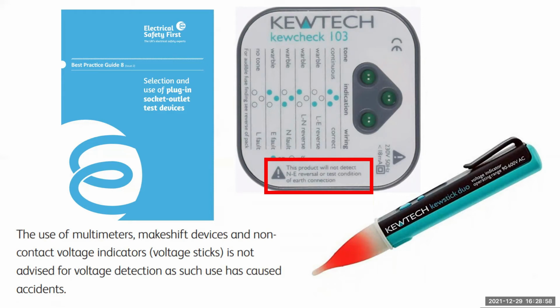It is worth noting that non-contact voltage indicators can be useful for identifying if a cable is potentially live without having to gain access to live parts, but if the stick does not illuminate, you cannot assume that the cable is dead and should instead proceed with caution and assume that it is live until proven otherwise. Although cables with a metallic sheath, for example FP, SWA or SY flex, can shield the volt stick from picking up the electric field required to make it work, so it may not be suitable for those cables. They are also handy for identifying if a Class 1 metallic accessory or enclosure has been earthed, as they will illuminate when touched against the enclosure.